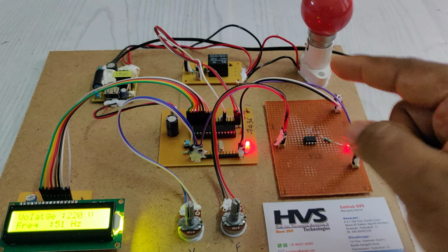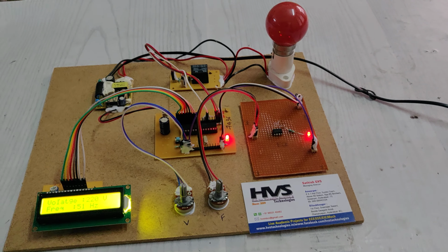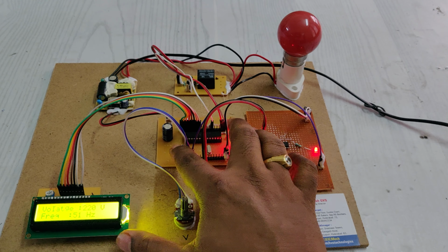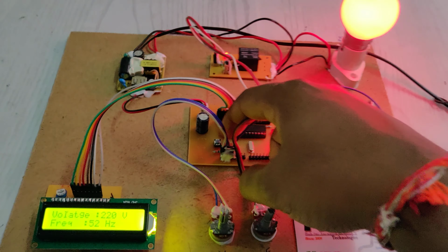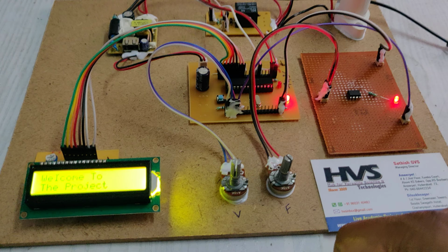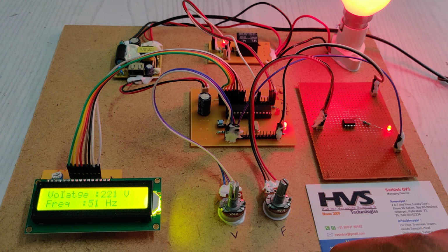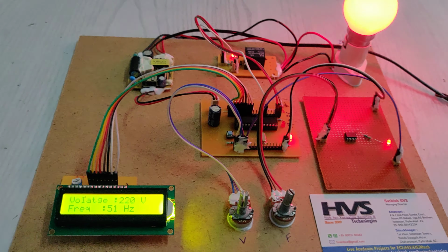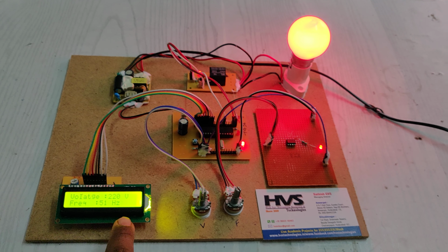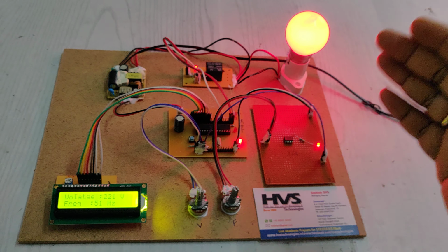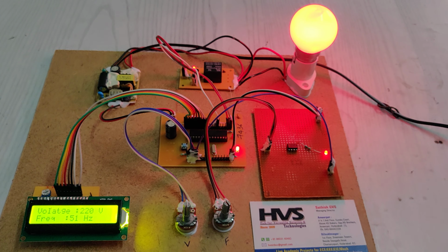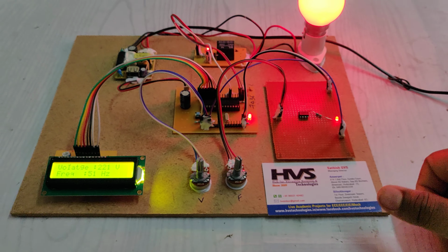But the power supply won't be resumed directly to the load automatically. Why? Because in electrical power supply, auto reset should not be there. This is the reset switch. Whenever an abnormality is detected, it will turn off the power supply to the load. After everything is set normally, we should reset the system once everything is cleared. On the LCD we can see that everything is normal. So the grid output is connected to the load section, whether it is distribution or the load section.